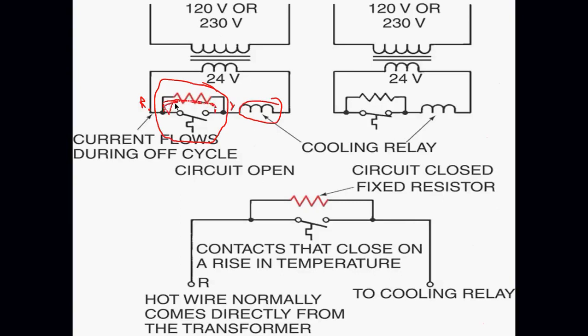Everybody understand now why I wanted us to talk about bypass? This cooling anticipator resistor is right there. When my thermostat is not calling for cooling, it's going to heat up that resistor. Again, not red hot, but it's going to provide a slight amount of heat to the thermostat. So the thermostat is going to think that the room is slightly warmer than it actually is. What this does is close the thermostat a little bit early. It anticipates the need for cooling.